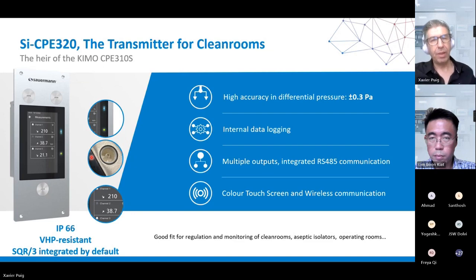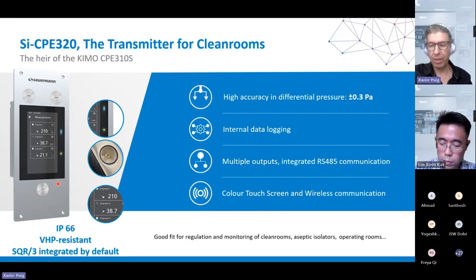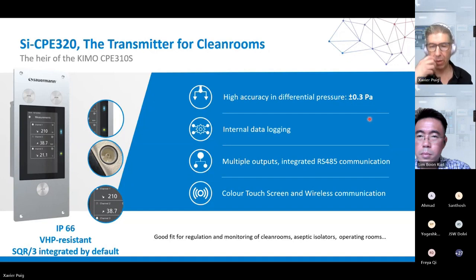Going on to the CPE, it's basically the same new features that we have on the C320. We also keep from the previous generation of products the front face pressure connectors. So you can calibrate the instrument, for example, from the front face. You can also connect from the front face to the PC with a cable. And obviously, the same thing: internal data logging, multiple outputs, adding the digital output as standard, touchscreen, and more importantly, we have increased the accuracy of the pressure measurement. We now have 0.3 Pascal as accuracy, which is really one of the best in the market today, if not the best.